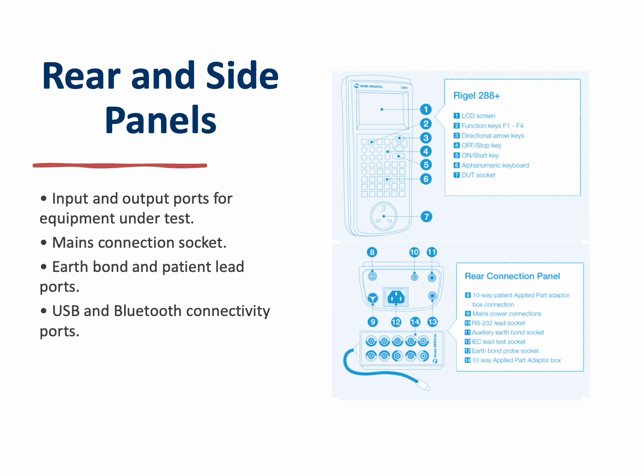Turning the Rigel 288 Plus around, the rear and side panels reveal the key connection interfaces. These include dedicated test sockets for equipment under test, patient lead ports, and an earth-bond terminal. The mains connection socket allows for leakage and power-on testing under simulated real-world conditions. A USB port enables data transfer to computers, while Bluetooth support allows wireless pairing with printers and barcode scanners. Each port is labeled and positioned to avoid cable clutter, making setup straightforward. As a general rule, before starting any EST, it's good practice to familiarize yourself with these connection points to ensure proper grounding and accuracy.